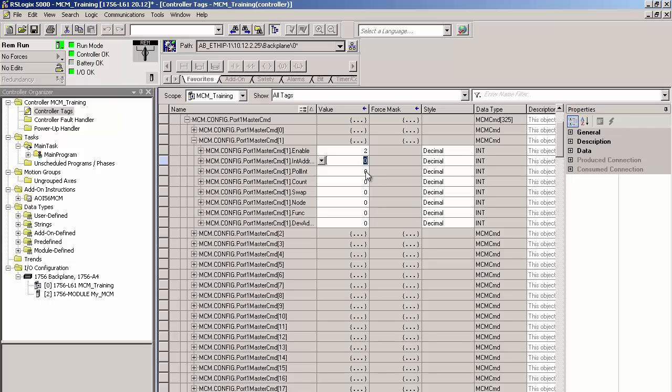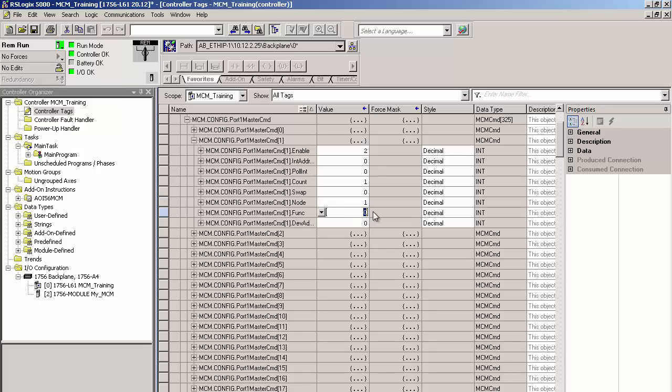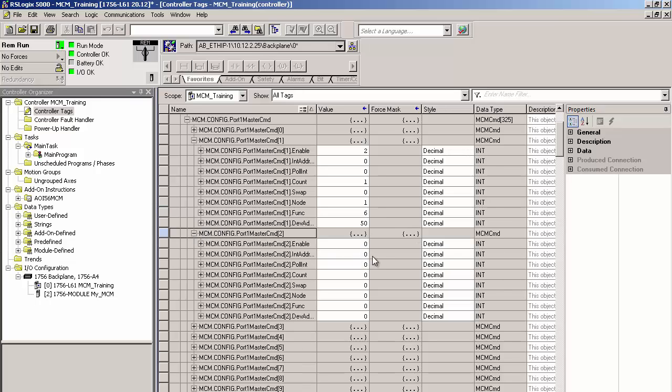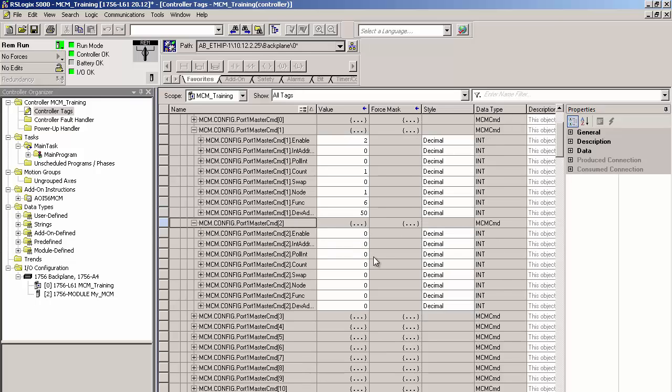I'll enter an internal address of 0, which is where the register will be written from in the MCM's database. This is also the starting address for the MCM's write data section. I'll enter 1 as the number of registers I want to use. I'll select node 1 as the device to give this command to. I'll use function code 6 to write a single holding register. Finally, a device address of 50 means I'll write the registers to slave address 40,051, which is the register where the limit for phase A voltage is stored in the power monitor.